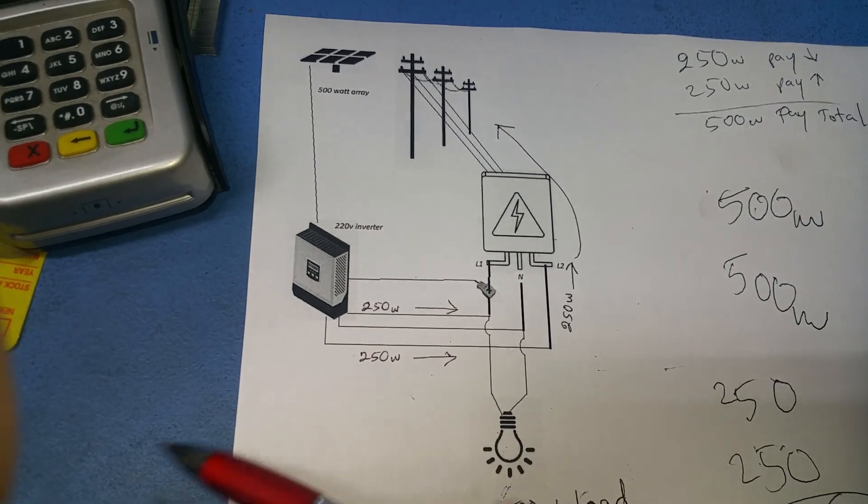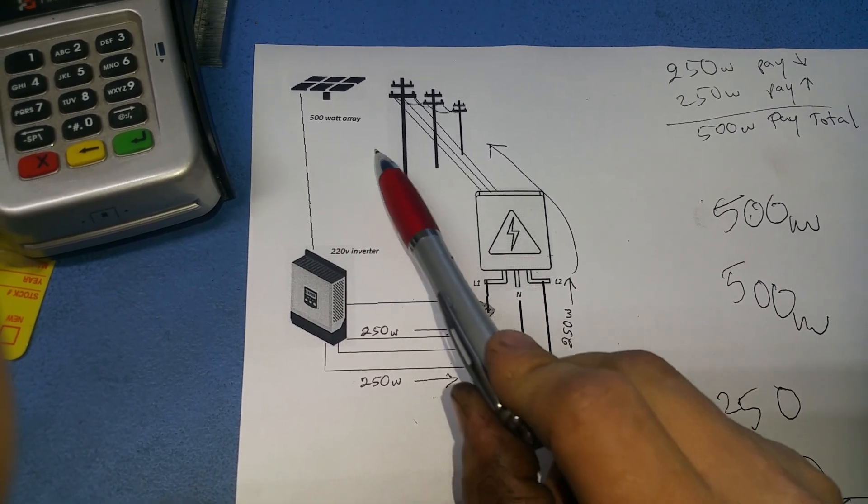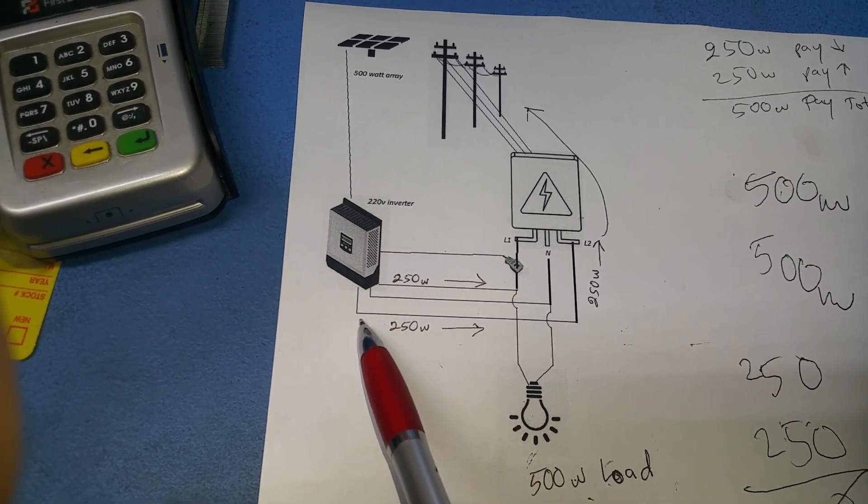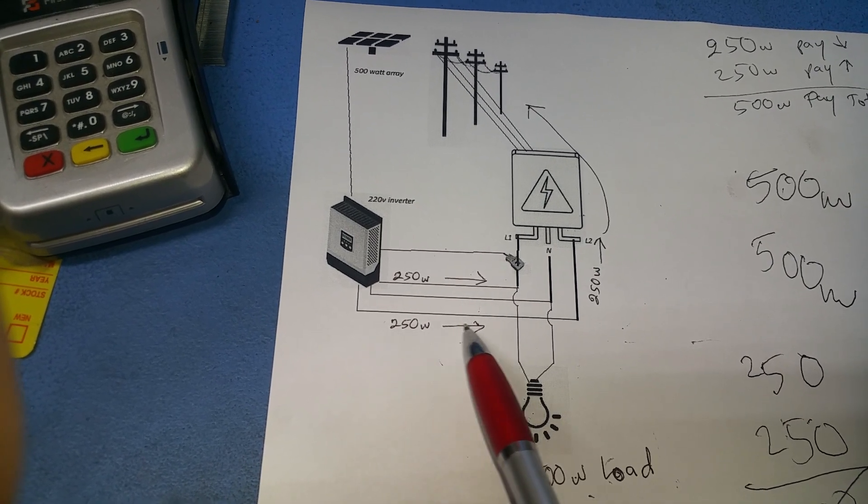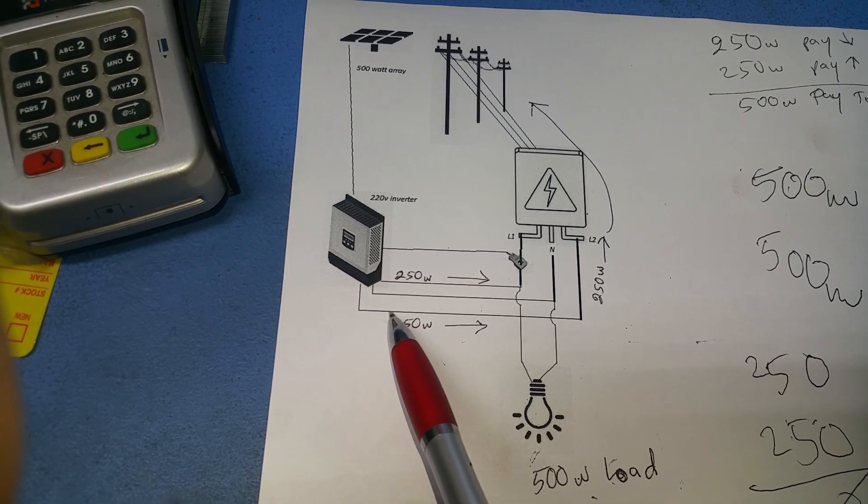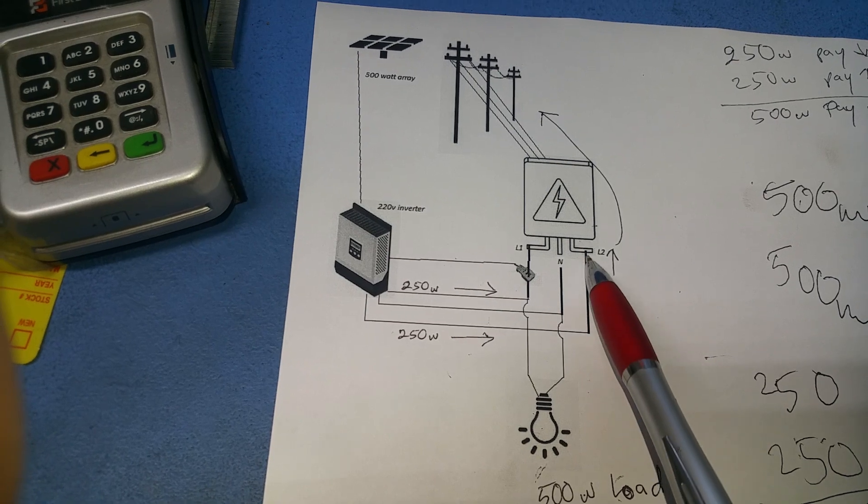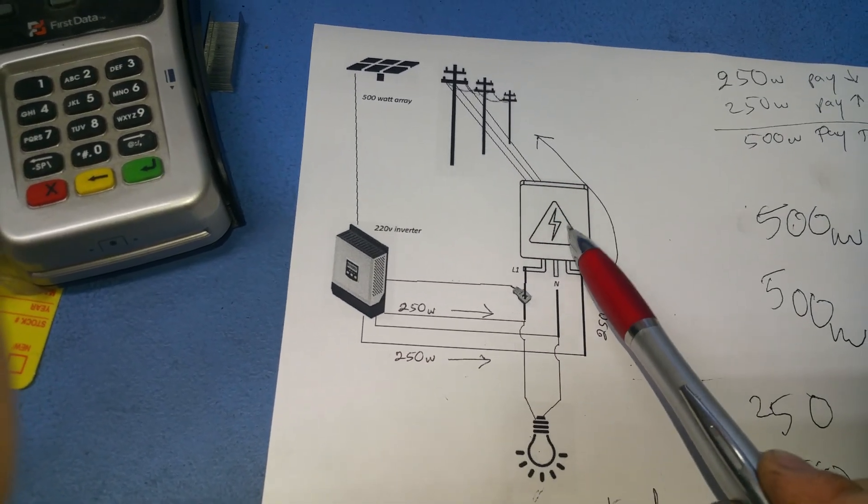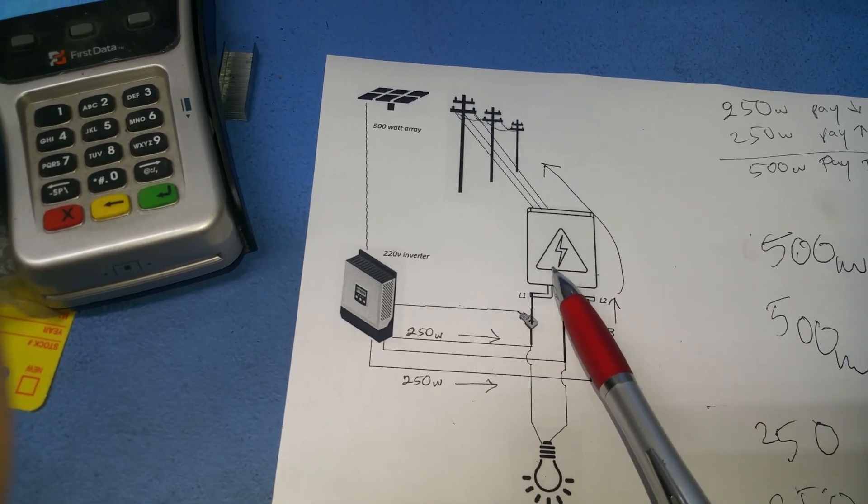However, what happens on the L2 leg? The inverter put out 250 watts on the L2 leg, and because there's no load on L2, this 250 watts actually feeds back to the grid. Because I don't have net metering, they will charge me for putting power back into the grid.